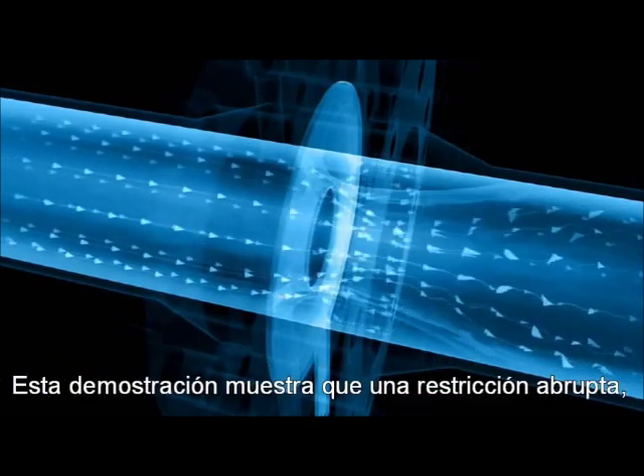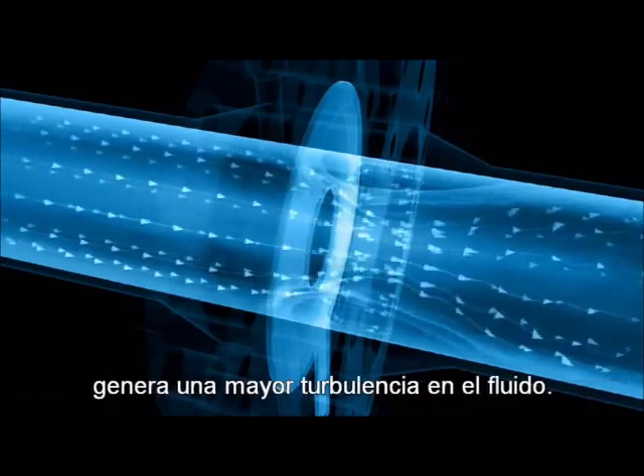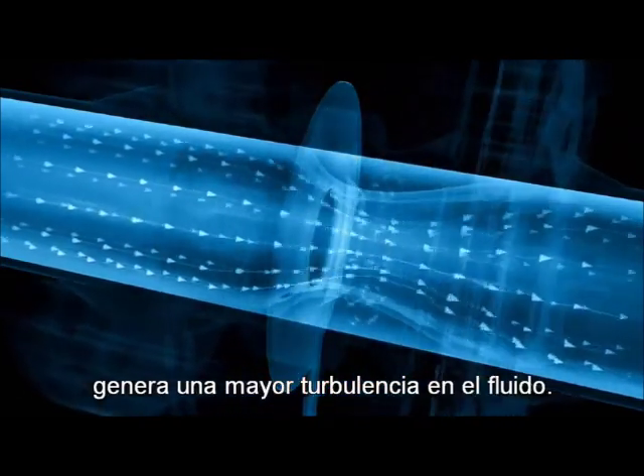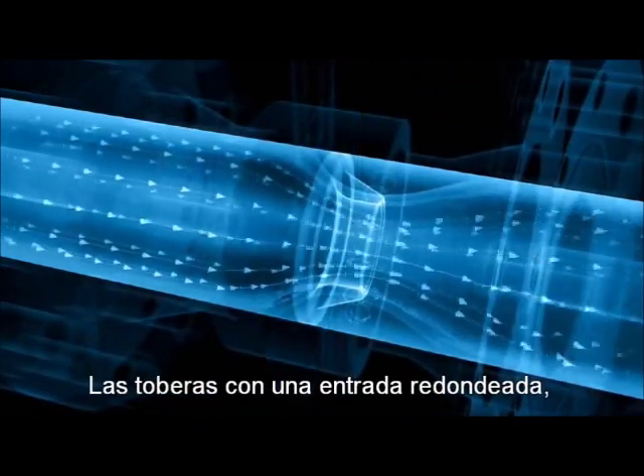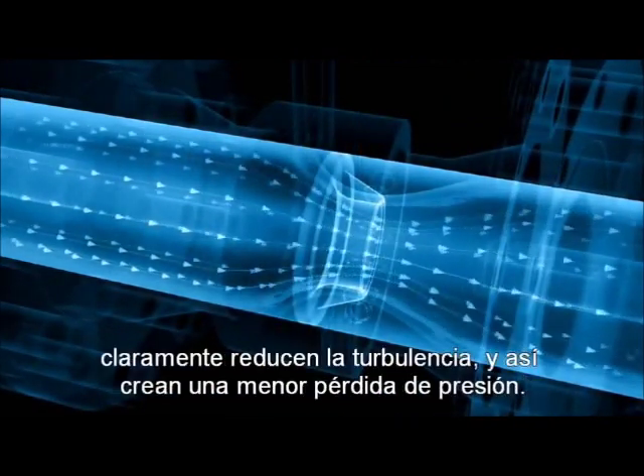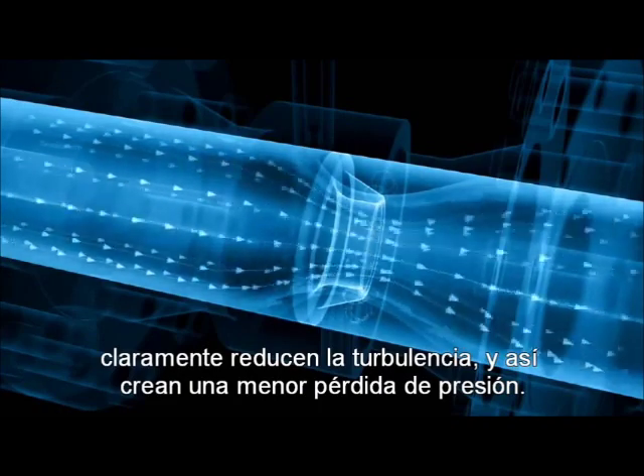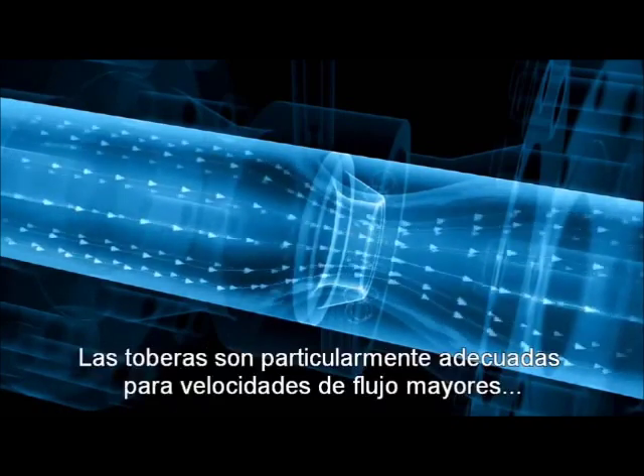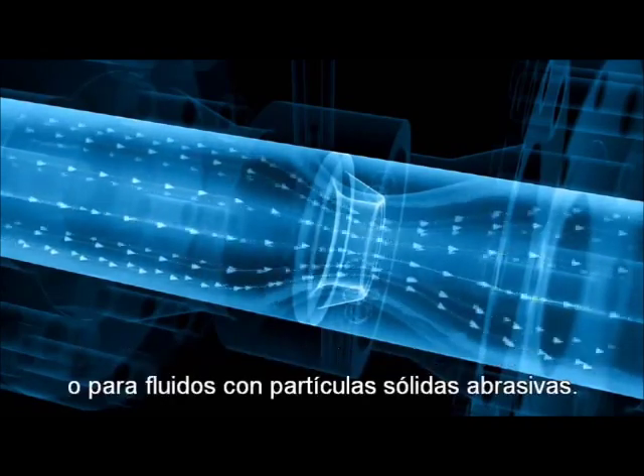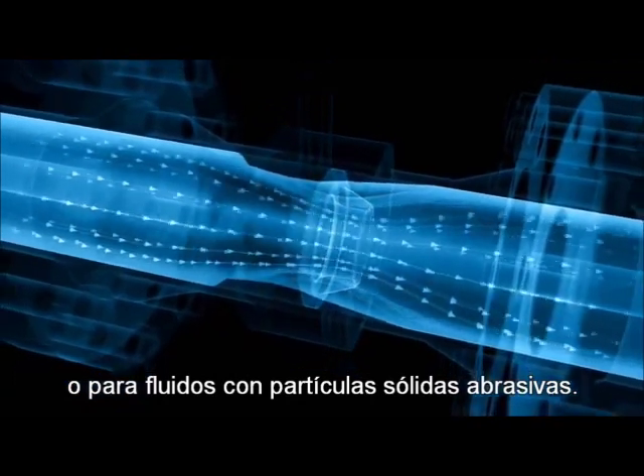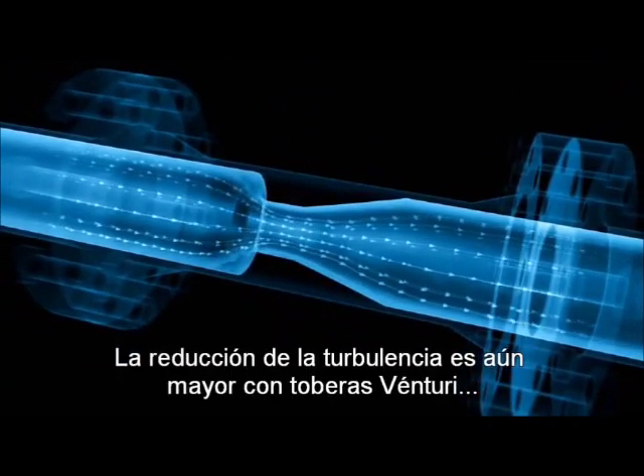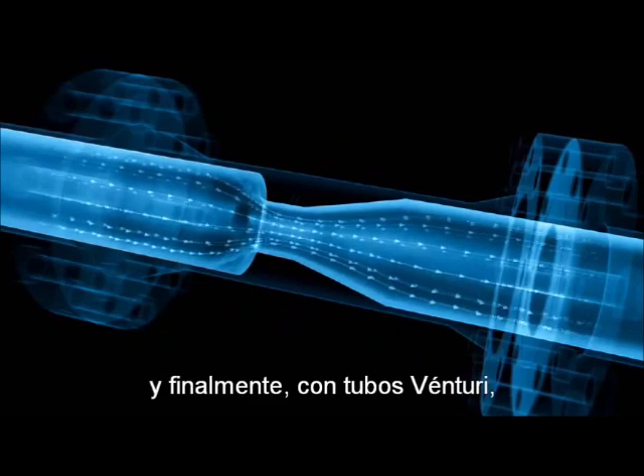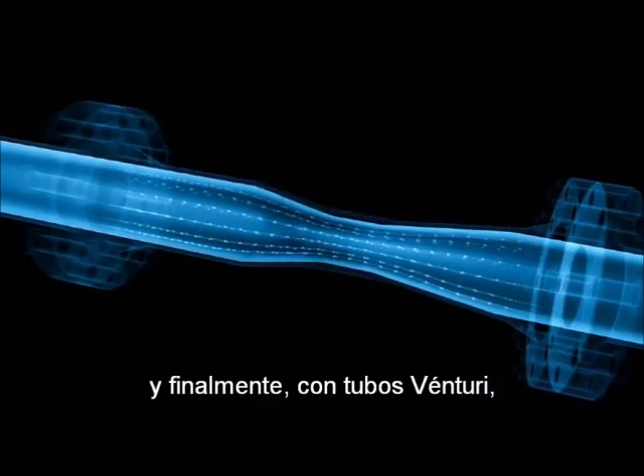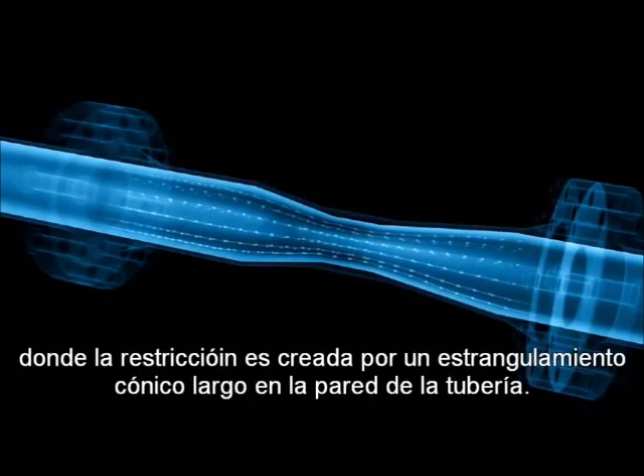This demonstration shows that an abrupt restriction generates severe turbulence in a fluid. Nozzles with a rounded, funnel-like inlet clearly reduce turbulence and thus create less pressure loss. Nozzles are particularly suitable to higher flow velocities or to fluids with abrasive solid particles. Turbulence reduction is even greater with venturi nozzles, and finally with venturi tubes, where the restriction is created by longer conical constrictions in the pipe wall.